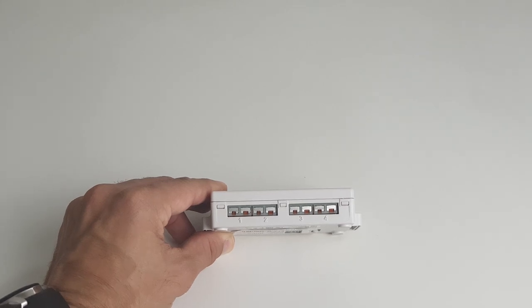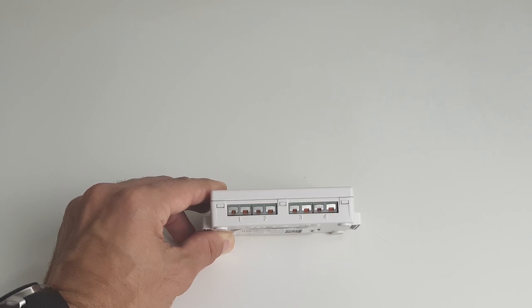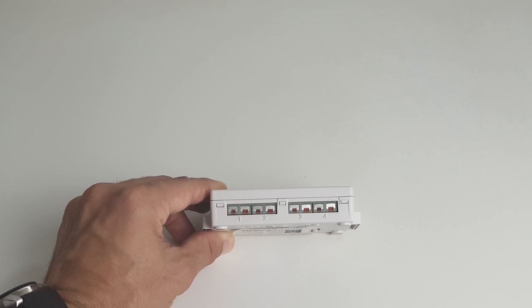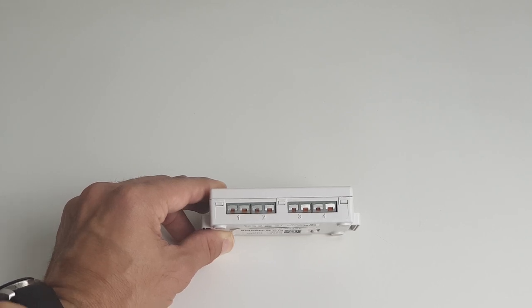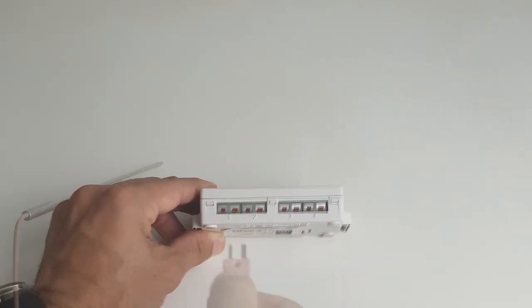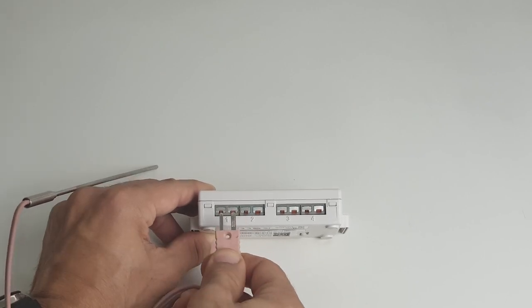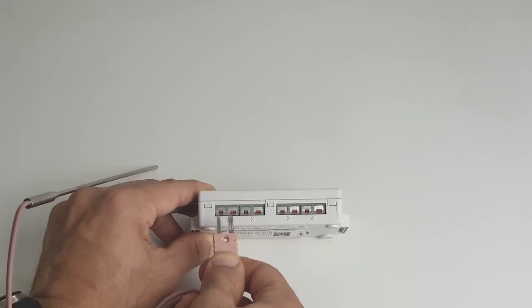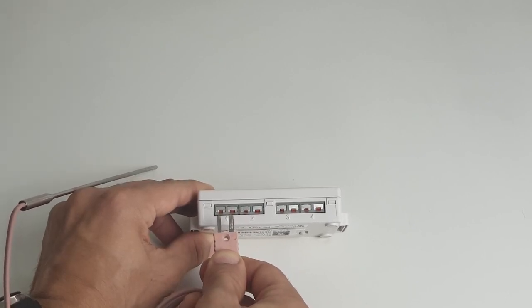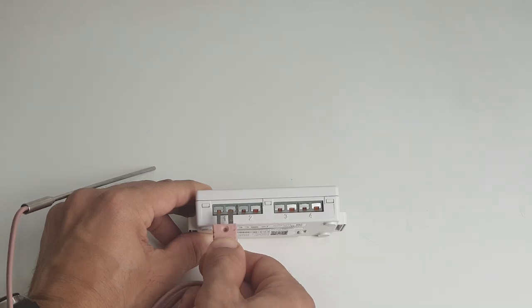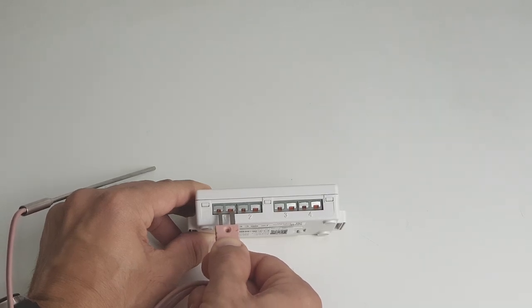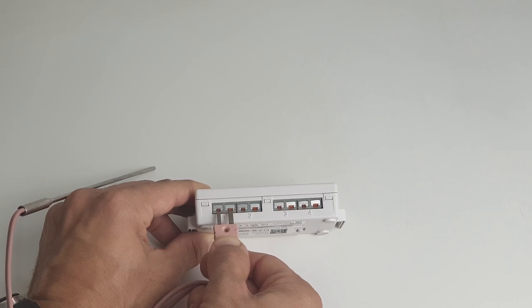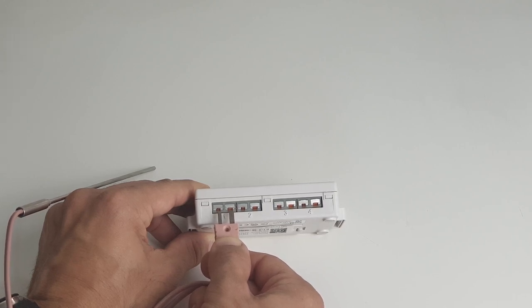The Hobo data logger has four miniature thermocouple inputs. Each input has two connections, one negative and one positive. If we get our thermocouple and plug it into the input, you see there is a wide end which is the negative and a narrow end which is the positive. The actual input connectors are accordingly wide and narrow. You can actually plug them in the incorrect way around if you force them in.